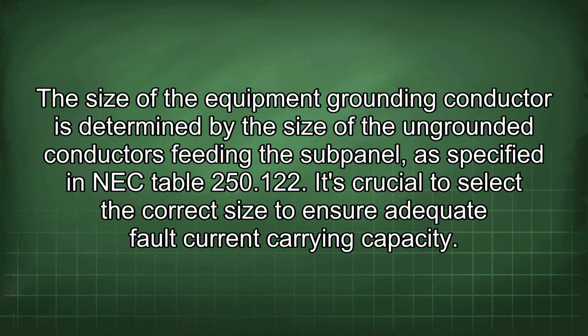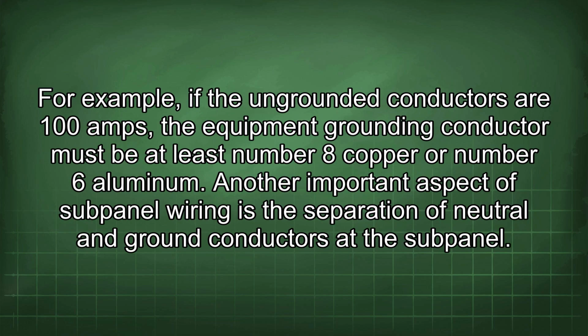The size of the equipment grounding conductor is determined by the size of the ungrounded conductors feeding the subpanel, as specified in NEC Table 250.122. It's crucial to select the correct size to ensure adequate fault current carrying capacity. For example, if the ungrounded conductors are 100 amps, the equipment grounding conductor must be at least number 8 copper or number 6 aluminum.